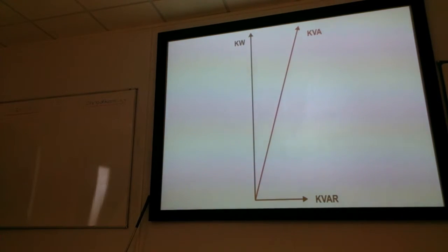Can you say those again, please? Yeah, sure. Kilowatts is real power, the actual power, effective power. kVAR is the reactance load, it's wattless power. And kVA is the total apparent power. So in order to use that much, if we've got that much reactance load, we've got to produce that much. So that's why we need to care about capacitors and inductors.